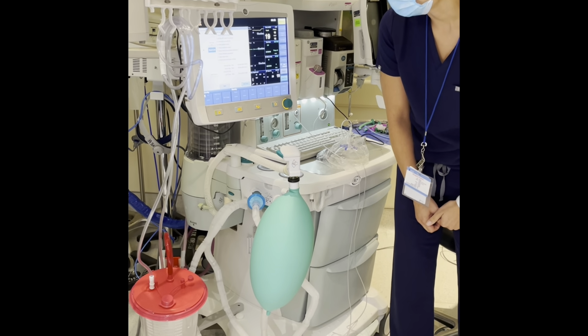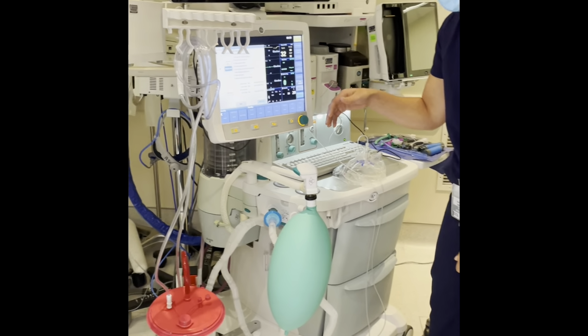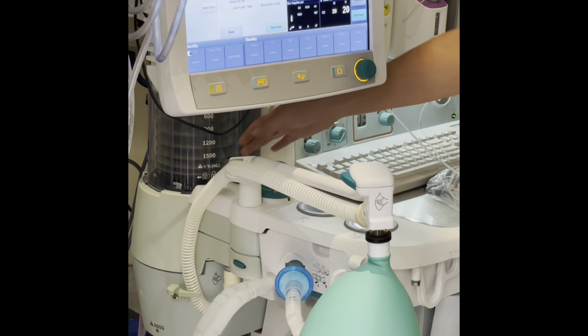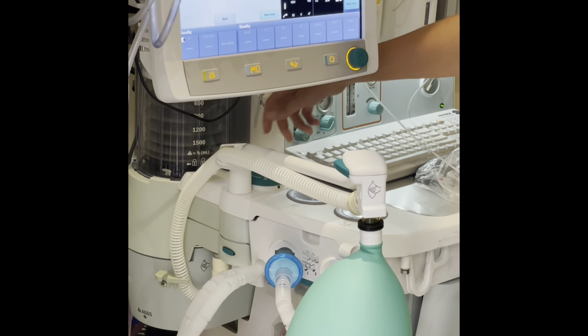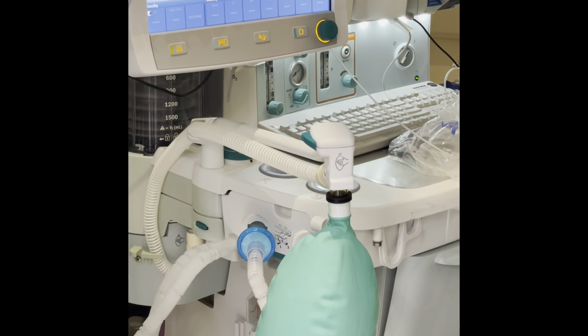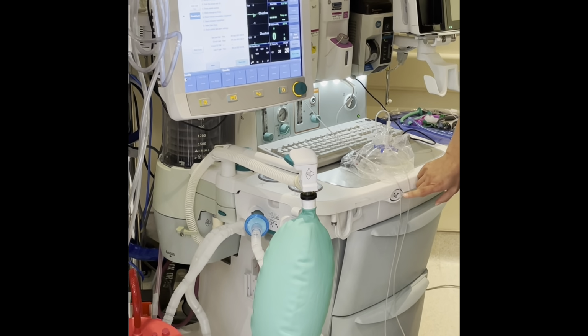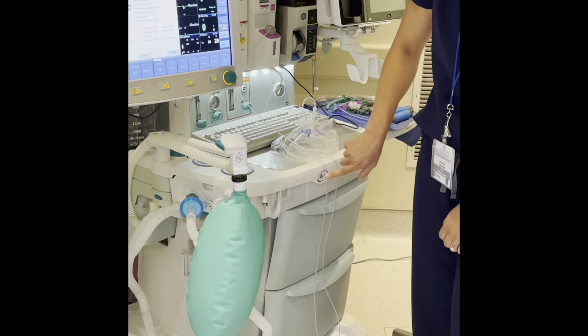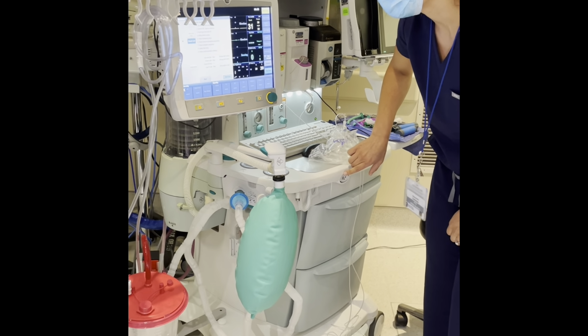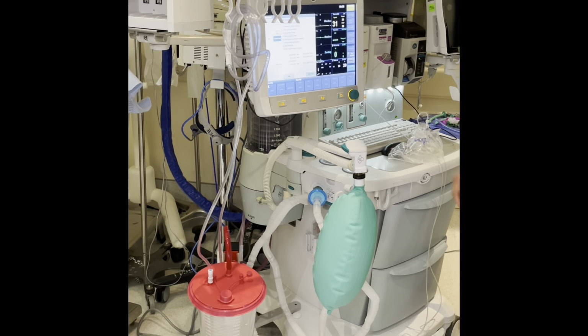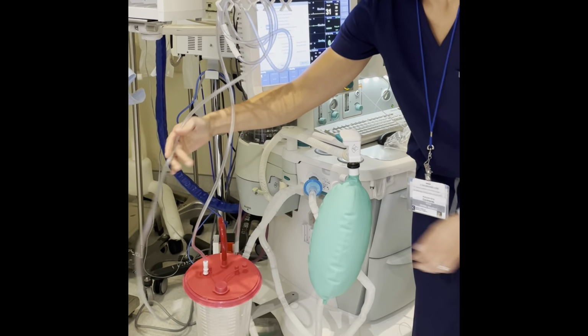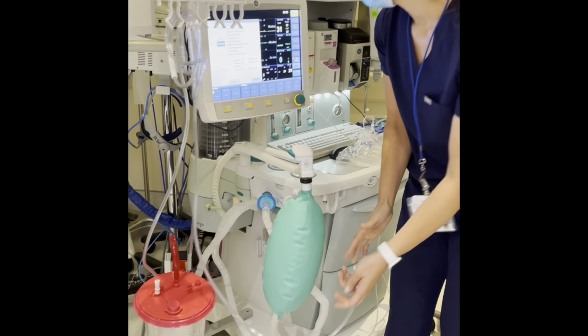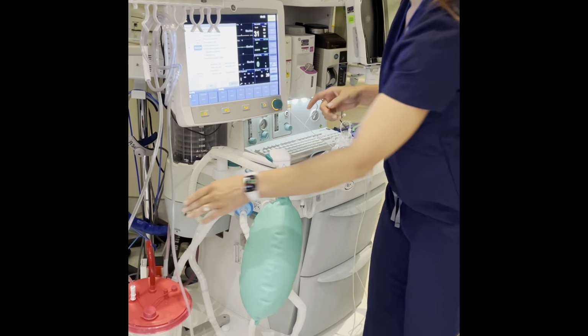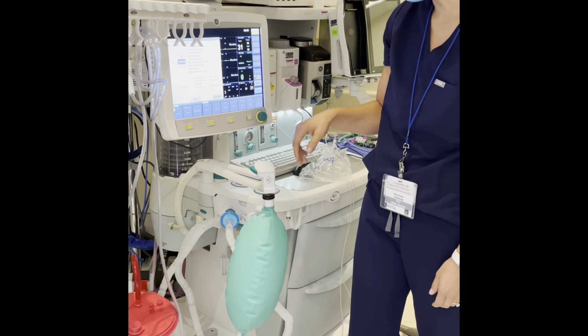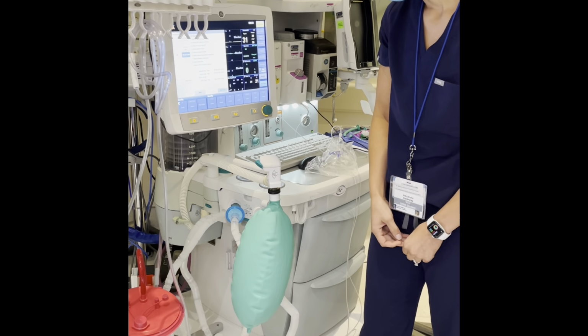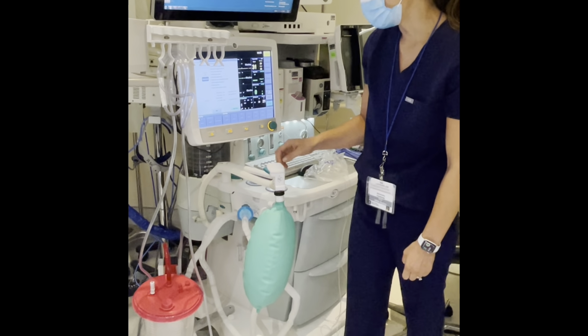Alright. Full test reminders. Go through all this as well. Alright, set the bag vent switch to bag, which it is. Set the APL valve to minimum. Flush the circuit with O2. You don't have to do that. Yeah, but that's where you do that. Check patient suction. We'll check that later. Just read through the prompts and then we'll go through, okay? Check emergency drugs, check manual resuscitation equipment, check intubation equipment, select start case, check control and alarm settings.